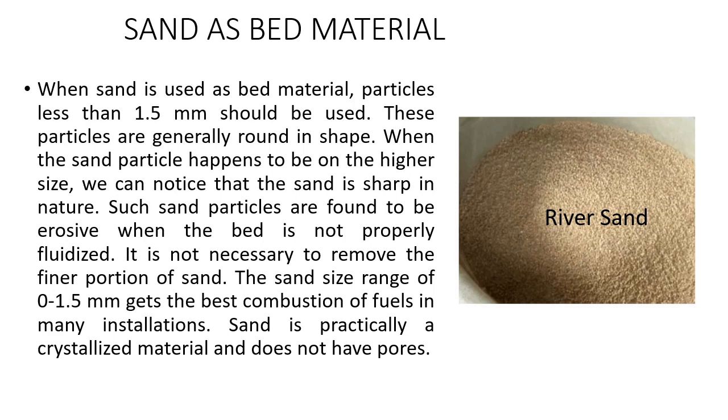It is not necessary to remove the finer portion of the sand. The sand size range of 0 to 1.5 mm gets the best combustion of fuels in many installations. Sand is practically a crystallized material and does not have pores.